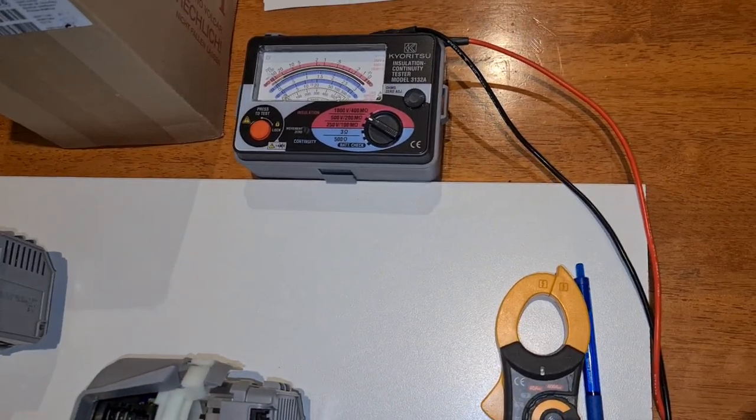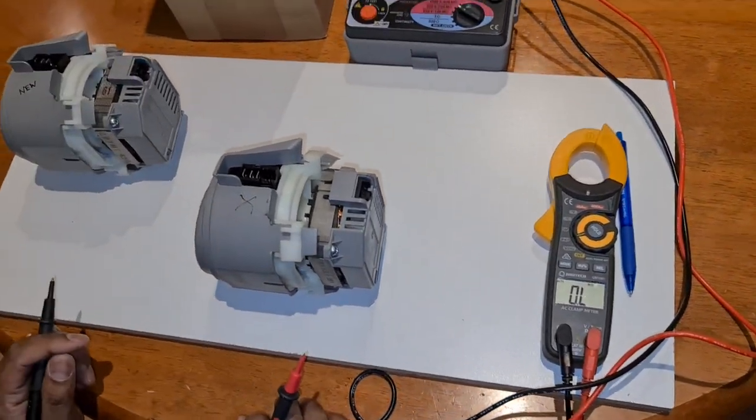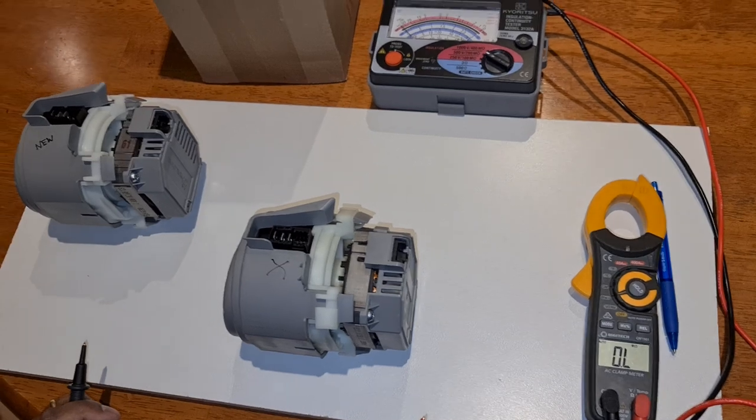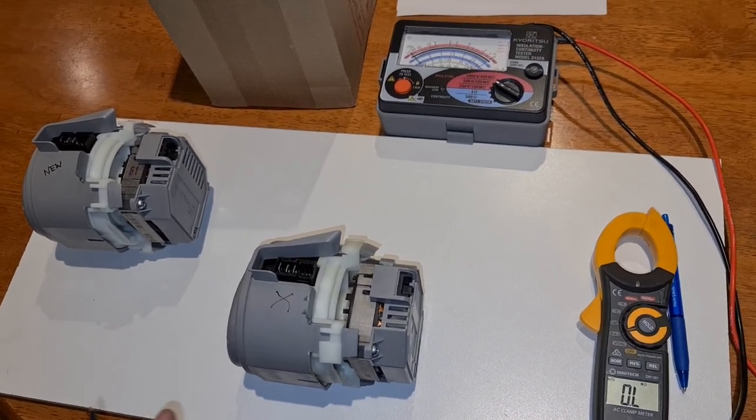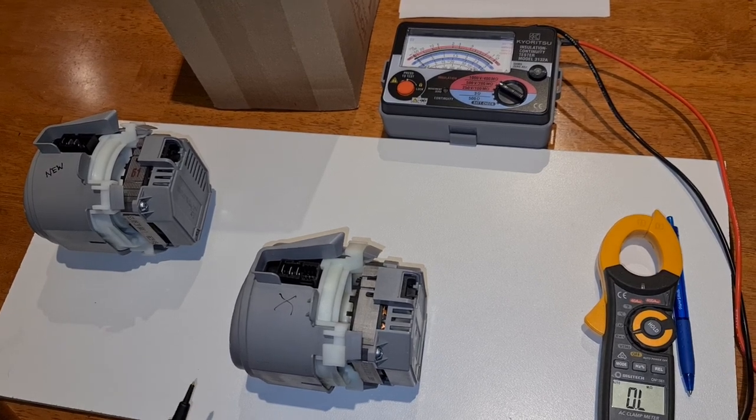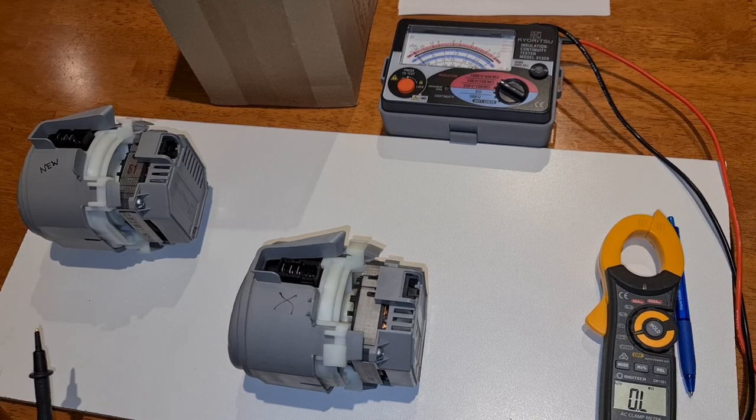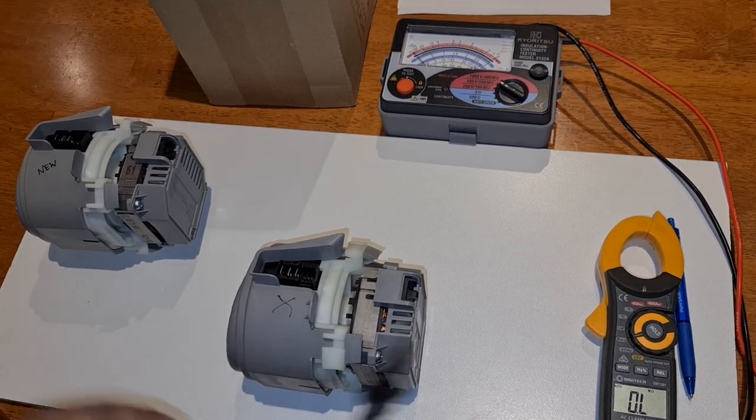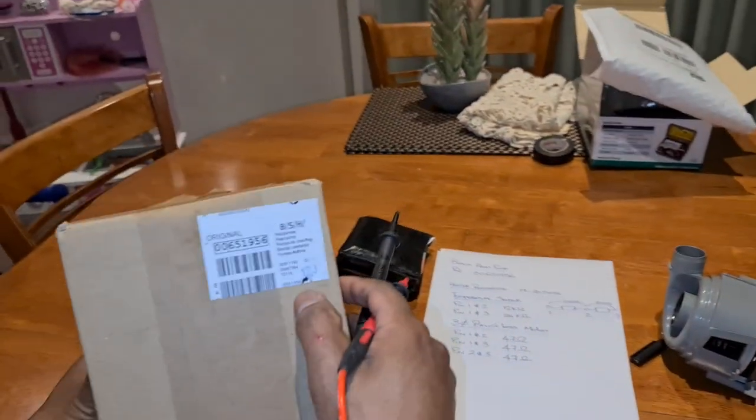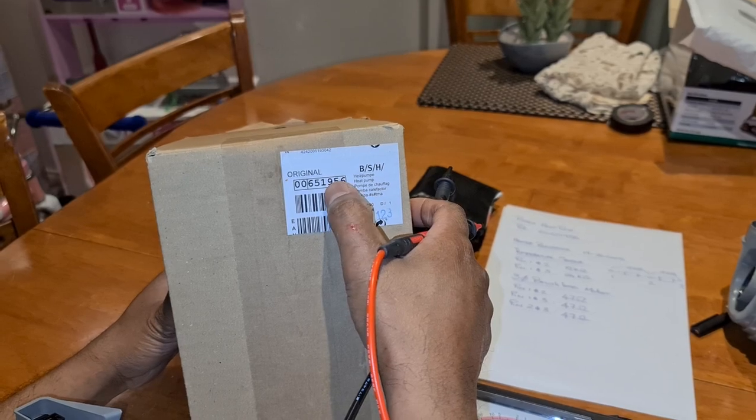So the multimeter method, if anyone tells you to use the multimeter to do insulation testing, it's a device that's not designed for that purpose. So this is how we do some basic testing to verify that the heating element is actually working properly on a Bosch heat pump. And the particular pump that we're looking at over here is 00651956.